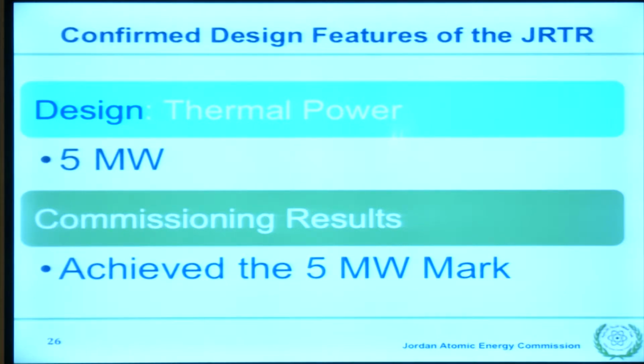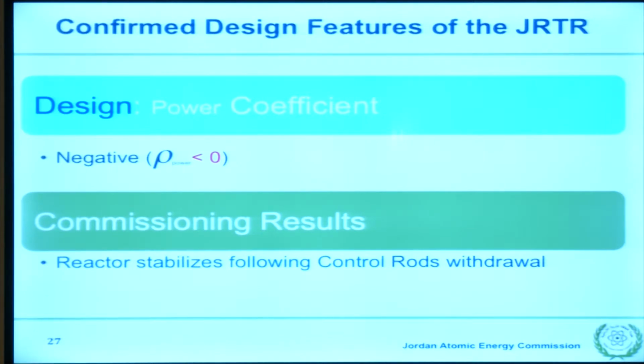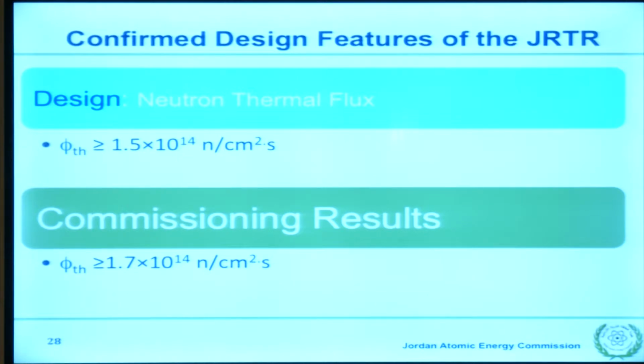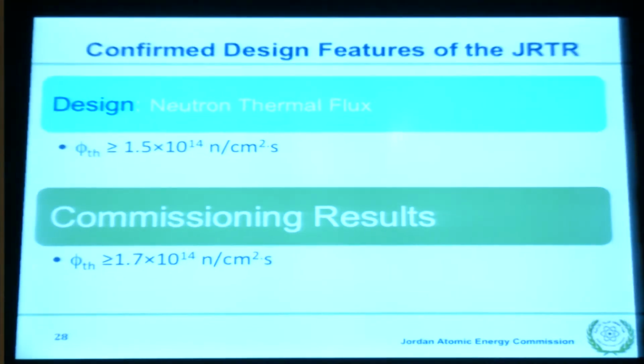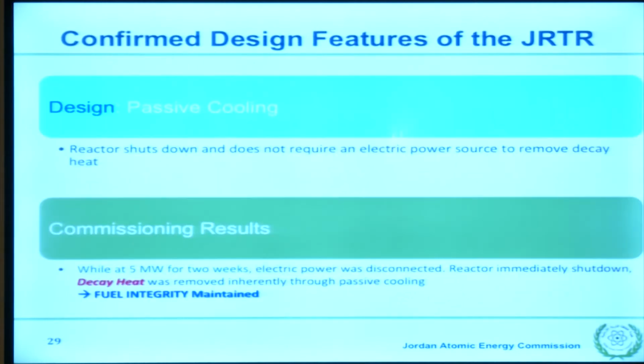We undertook commissioning tests last year, from April until December. All design features were met in terms of negative thermal power coefficient, meaning the reactor is stable, which is now a new requirement for regulators. The reactor stabilizes following complete control rod withdrawal, and we exceeded the design requirement for neutron flux, reaching 1.75 instead of 1.5, and also achieved passive cooling, an important consideration after the Fukushima event.